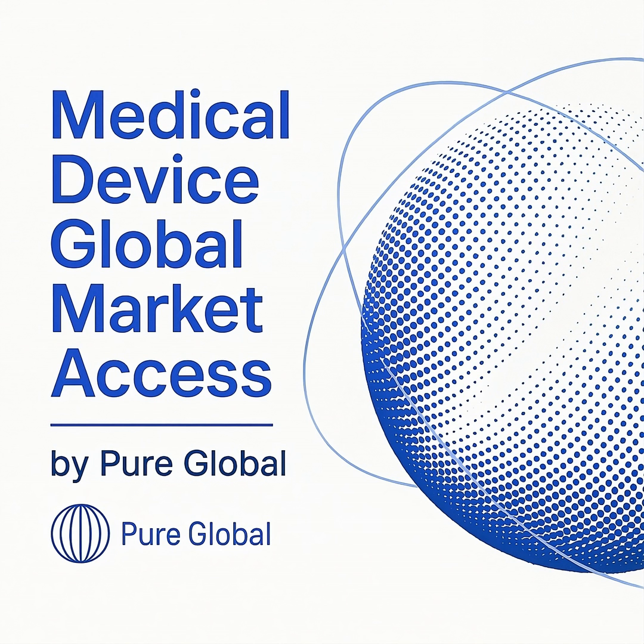You must provide a robust, evidence-based justification for why a PMCF study is not required, or alternatively, present a detailed plan that clearly addresses any residual risks identified in your risk analysis and gaps in your clinical evidence. Failing to connect your PMS activities back to your CER and risk management file is a critical oversight.